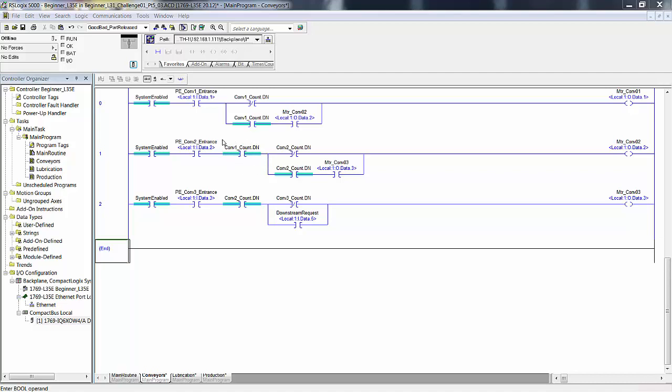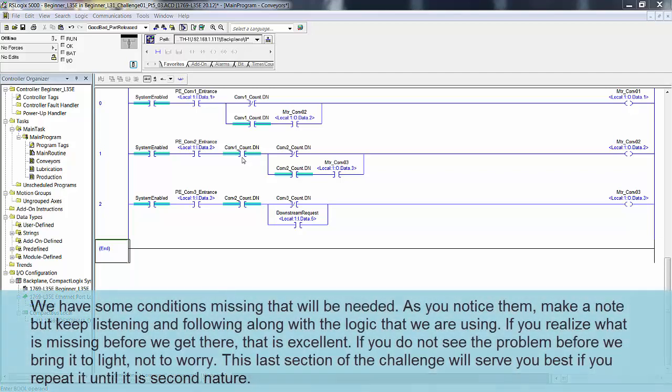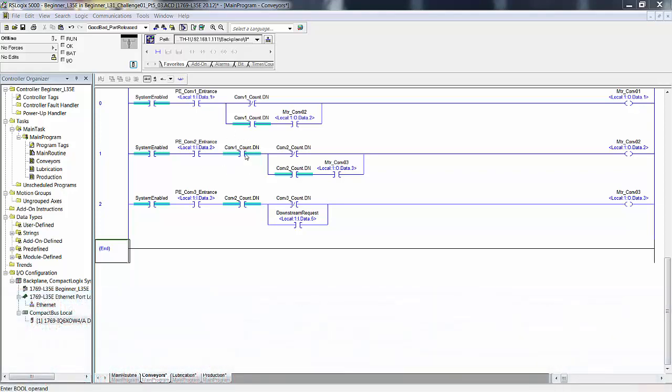Dropping down one rung, we now have the full state of conveyor one to consider. This bit here is kind of a logical pivot - it depends on whether you want to fill up all three conveyors one carton at a time or just buffer the first of the three conveyors. We're not going to run conveyor two unless conveyor one is full, meaning we have to completely fill up one before we run two. That's anded with photo eye two being blocked at the conveyor two entrance. If there's a carton blocking the entrance of photo eye two, you have to ask how did it get there.